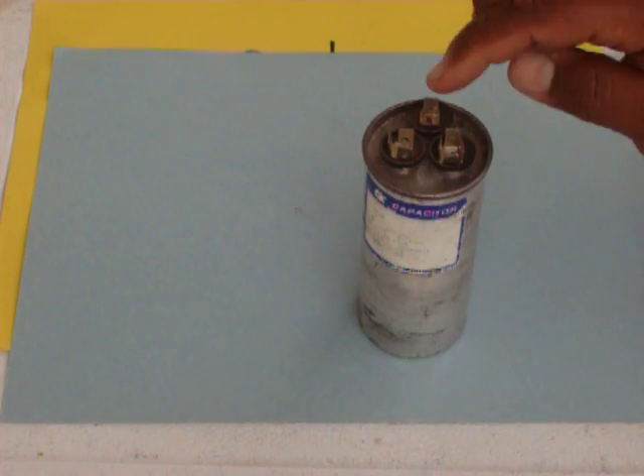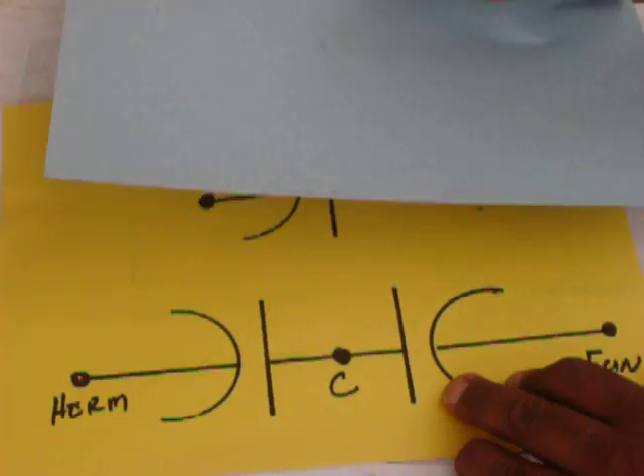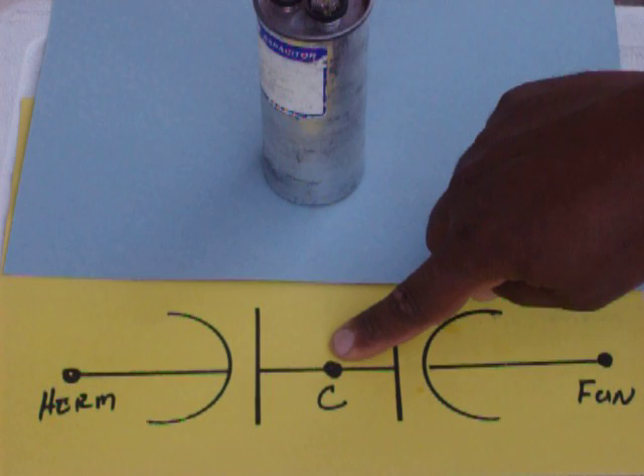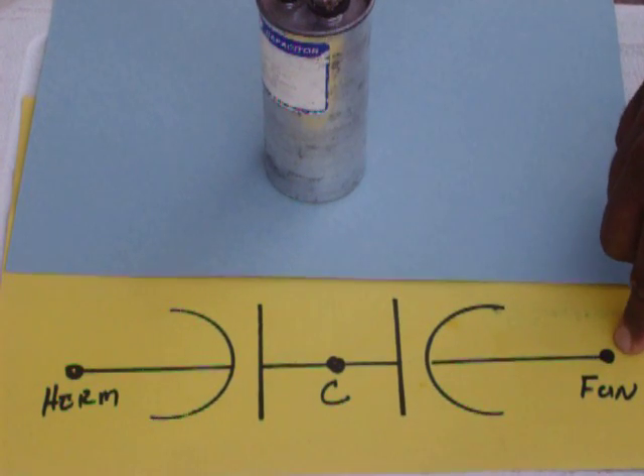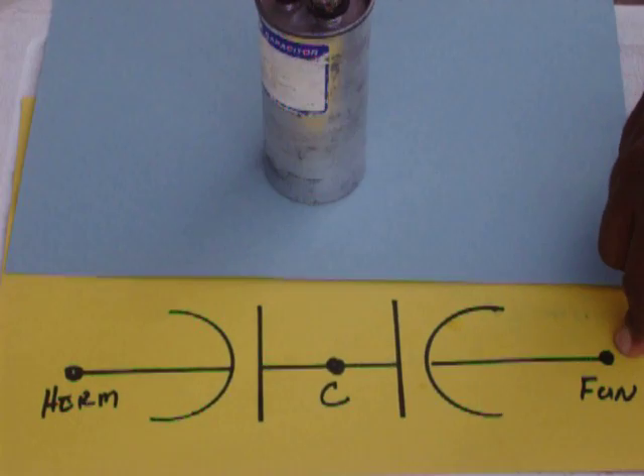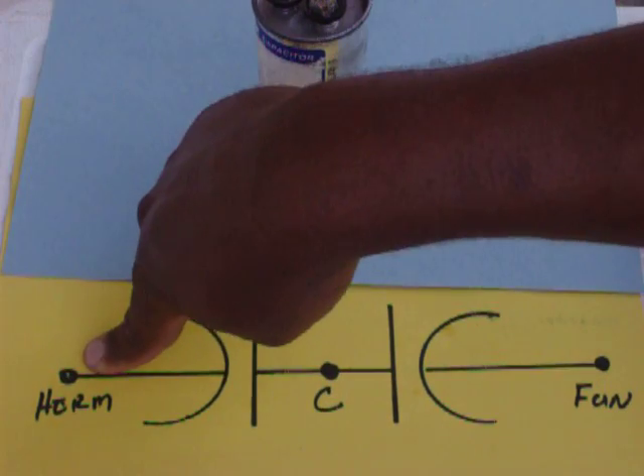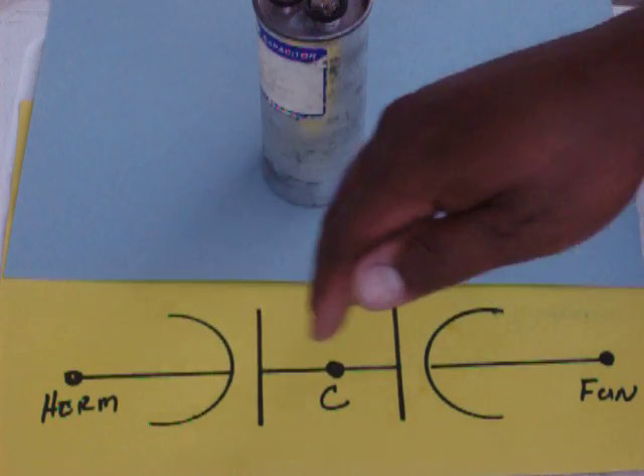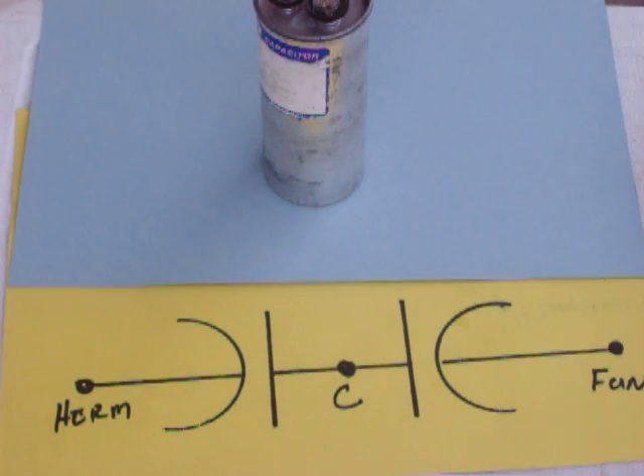This one feeds two loads. Power comes in. Power goes to two separate loads. This is the symbol for that. Power comes in at common. This side says fan goes to your outdoor fan motor. The side that says hermetic goes to your compressor. So what it is, it's two different capacitors built into one with one common terminal.